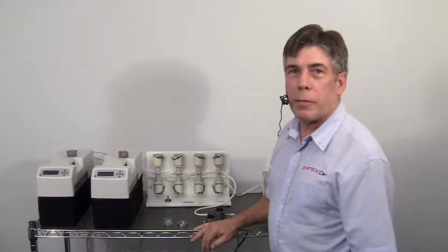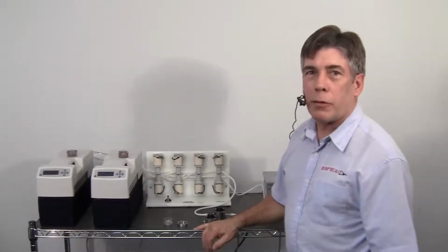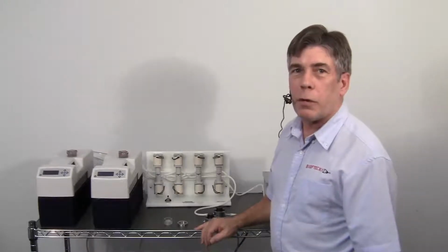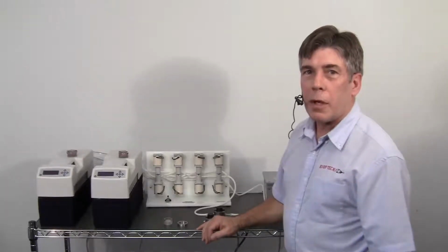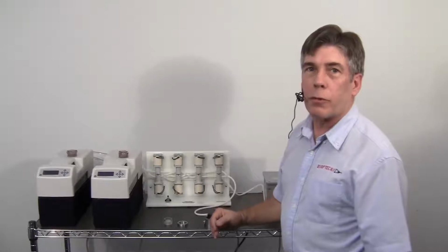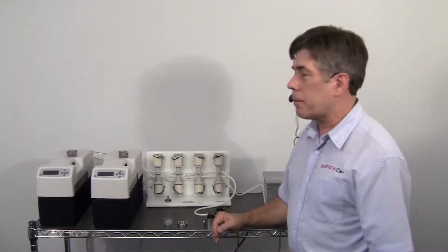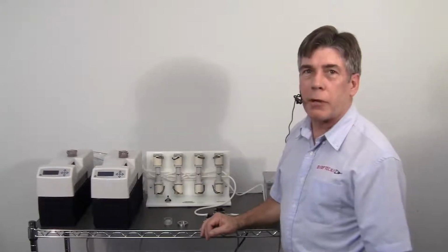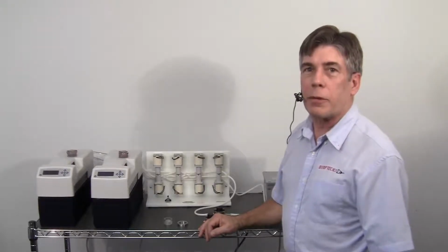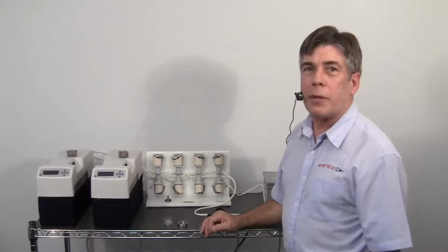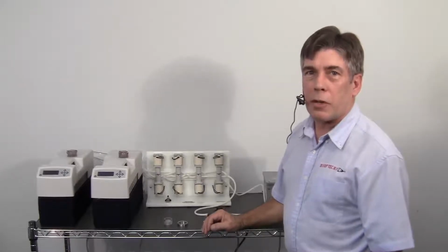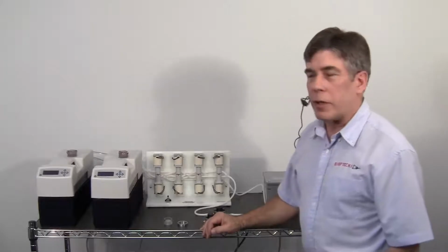I'm the engineer here at Bioptechs, and I'm going to introduce you to a system that we developed here for a customer that needed to observe worm embryos and temperature transitions for those worm embryos on a microscope. The scope they're using is using high numeric aperture objectives, therefore they needed to have a cover slip surface and a very rapid temperature change capability for the specimen at the specimen plane. The way we've done this is to set up two nanotherm systems.